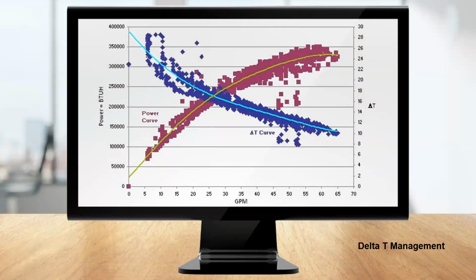So let's suppose we had a delta T limit of 12 degrees, but the valve has overflowed and the delta T is now closer to 10 degrees. The coil is currently using about 63 GPM. The delta T manager detects a delta T lower than that threshold or that set point and will reduce the flow. As the flow decreases to about 55 GPM, the delta T rises to the set point of 12 degrees, and the power output stays relatively constant, taking advantage of that flatness of the coil curve, as we discussed earlier. But let's note, we must pick a delta T set point appropriate for the coil. If we selected a 16-degree delta T on this coil, we would certainly starve that space.